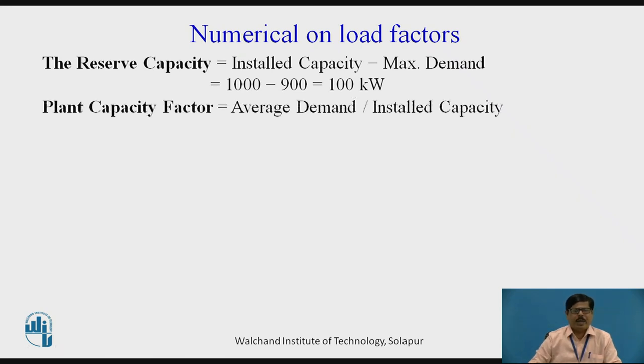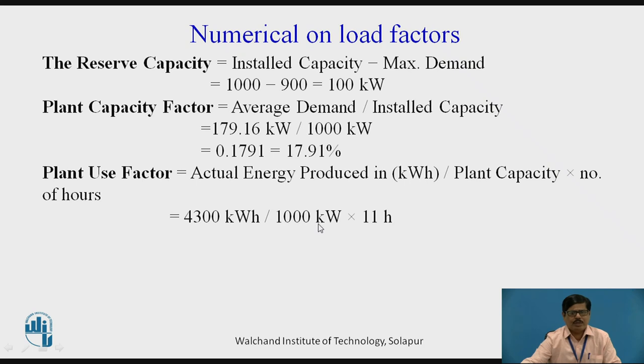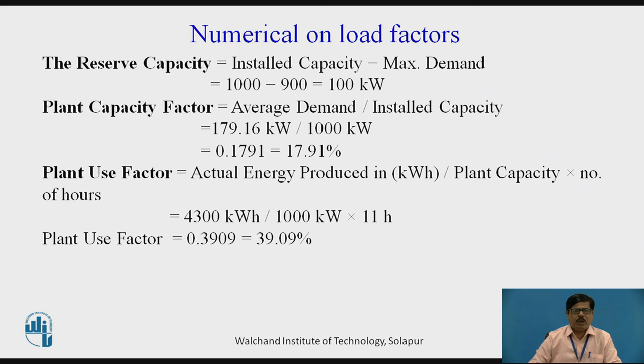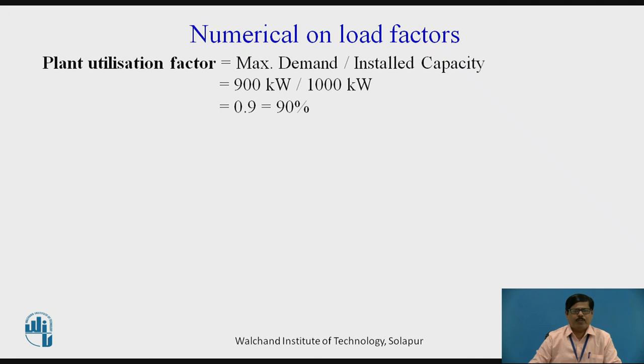Plant capacity factor is given by average demand divided by installed capacity. Average demand is 179.16 KW divided by installed capacity of 1000 KW, so the plant capacity factor is 0.1791, that is 17.91%. Plant use factor equals actual energy produced in KWh divided by plant capacity multiplied by number of operating hours. The actual energy produced is 4300 KWh, divided by installed capacity of 1000 KW, and the plant operates for only 11 hours — for the remaining 13 hours there was no load. So the plant use factor is 0.3909, or 39.09%. Plant utilization factor is given by maximum demand divided by installed capacity: 900 KW divided by 1000 KW gives 0.9, or 90%.